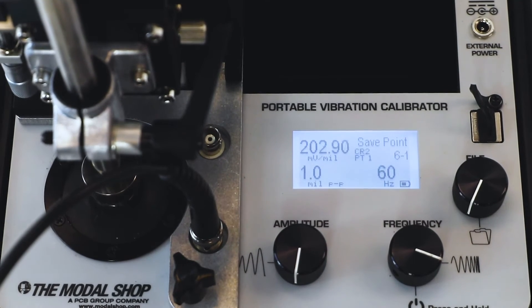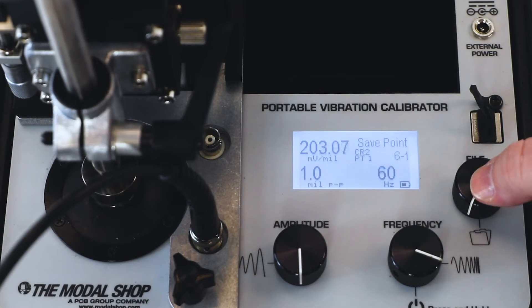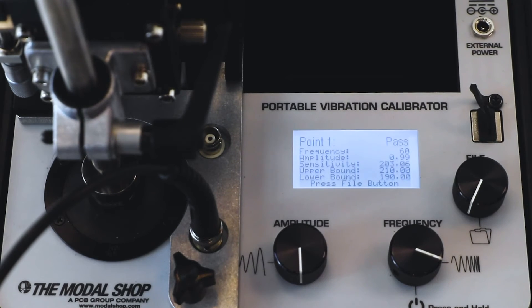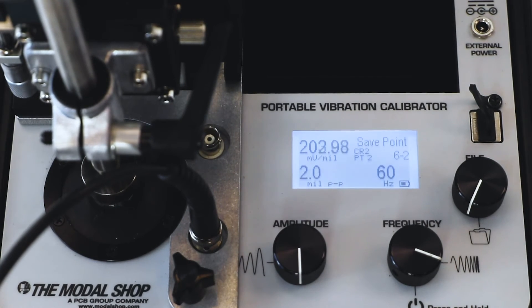We have the output of the Proximitor connected to the test sensor input of the shaker. Our first test point is at 1 mil peak to peak at 60 hertz. You can see at the top left of the screen, our sensitivity is about 203 millivolts per mil. When I press the file button, the point saves to the memory of the calibrator, and the device tells us whether or not the probe passes or fails. In this case, the ProxPak passes because it's within plus or minus 5% of 200 millivolts per mil — so anything from 190 to 210 millivolts per mil passes, and we measured about 203.